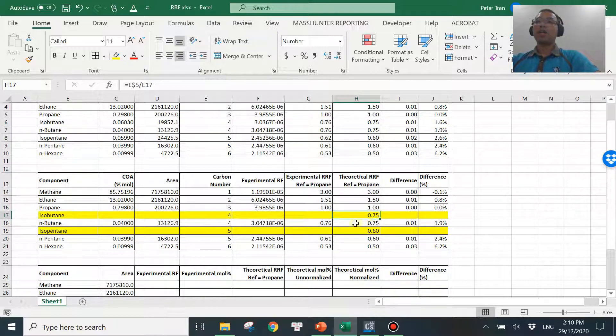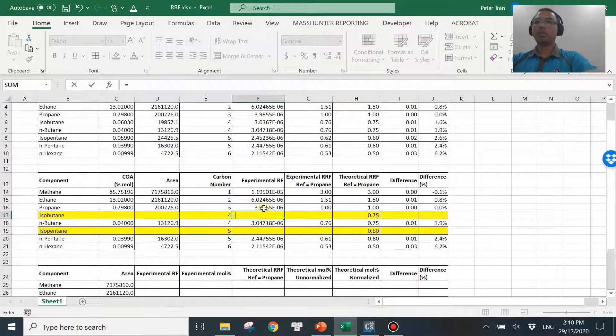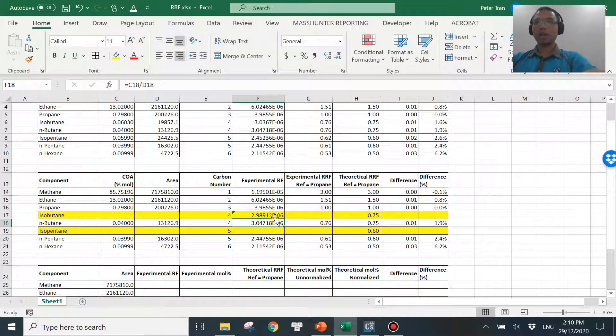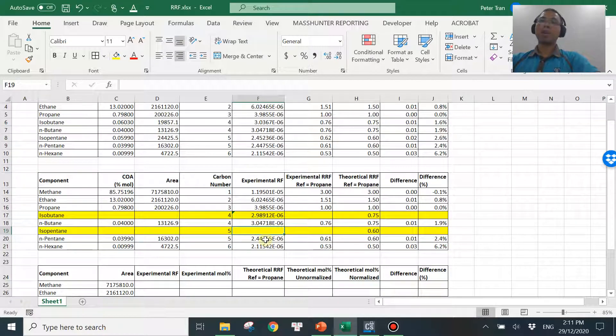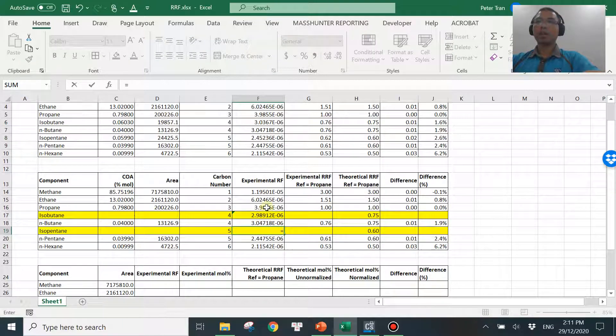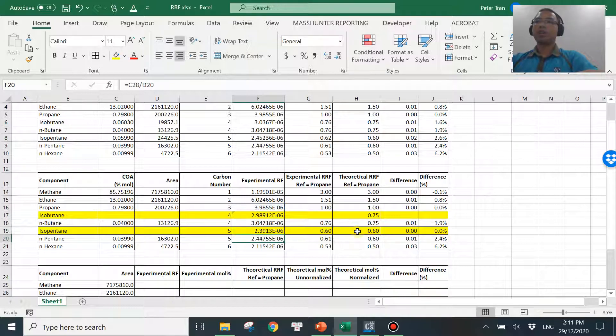Because you know the relative RF, and you know the response factor of the reference, the experimental RF of the unknown is very easy — it's just the response factor of the reference times the theoretical RF value. That's how you get this number, and you can see these two numbers are pretty close as well. The same thing applies for isopentane. If it's isopentane vs. n-pentane, you can just copy the value of n-pentane over. But in a more generic situation, that would be the response factor of the reference times the relative response factor theoretical value. You get this number, and these two numbers are actually quite close to each other. That's the way you can estimate the response factor for unknown compounds that you have no way to purchase in a calibration standard.